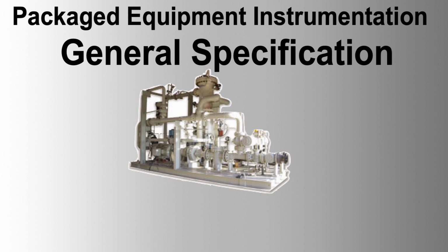All instruments must comply with the electrical classification of their installation area and be certified accordingly. Transmitter communication should be 4 to 20 milliamps, two-wire. The PLC shall communicate with existing DCS equipment using Modbus RTU protocol via RS-485 redundant serial link. Start-stop trip signals from DCS ESD systems to the package unit shall be hardwired through potential-free relay contacts rated at 24-volt DC, 0.5 amp.